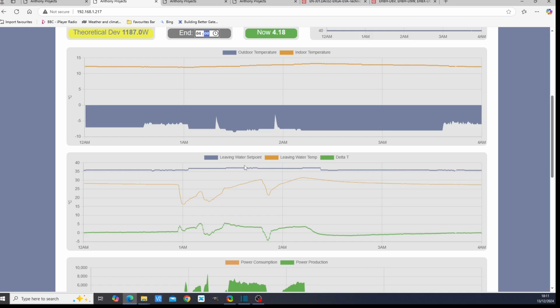And frankly, you don't need too much of a leaving water temperature to start your room temperature rising. In fact, you can do it with a leaving water temperature of 20 degrees, but you'll never have a leaving water temperature of 20 degrees. The lowest configurable leaving water temperature for your heat pump is about 25 degrees. So you're still going to have a thermostatic kind of characteristic of operation if you leave your house in holiday mode. And this is the coldest night that we've had so far, -8 degrees.